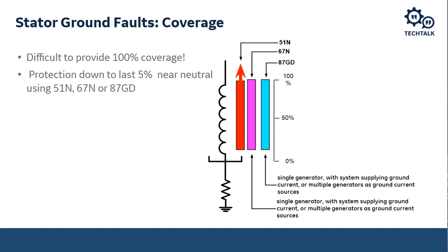If there's another ground fault somewhere else in the system, then you get a phase fault and you'll be able to detect that. However, obviously you risk collateral damage because now your two ground faults give you a phase to ground fault, phase to ground fault if it's on a different phase, and you can cause other high fault currents to flow in your system and cause other issues and collateral damage.